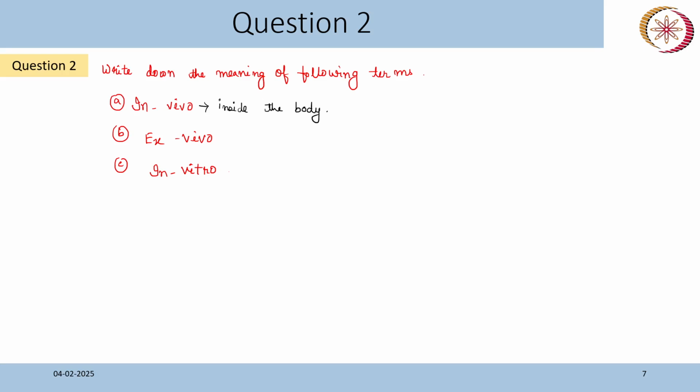So if you test your sensor in this manner in vivo, then you will get a very accurate result, because ultimately you want your sensors to be used on patients and persons, right? But for testing purposes, this is not a good idea. People used to do this testing on animals, which is kind of cruel. It's not appreciated.